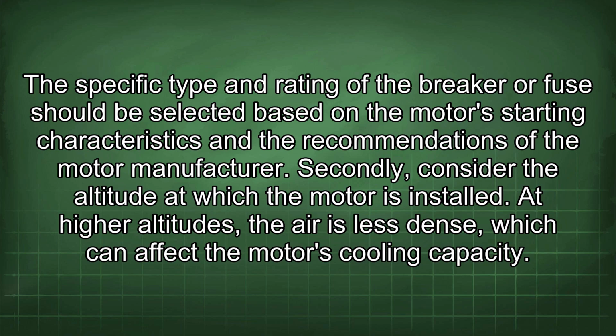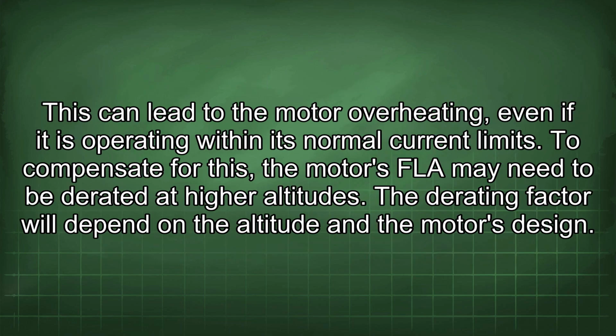Secondly, consider the altitude at which the motor is installed. At higher altitudes, the air is less dense, which could affect the motor's cooling capacity. This can lead to the motor overheating, even if it is operating within its normal current limits. To compensate for this, the motor's FLA may need to be derated at higher altitudes.